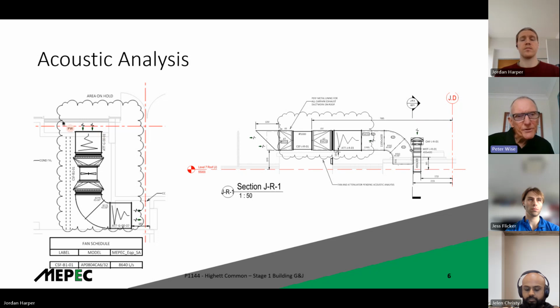Firstly, is this a louver along here? Yeah. So the distance between the louver and the intake to the attenuator should be, let's say, 1 metre - I don't know how much that is here. Then there's the orientation of the splitters in the attenuator, because this is a rectangular attenuator, they can be either horizontal or vertical. In this case they should be vertical because the air's coming through at different levels. If it's horizontal, some air wants to go through certain splitters and you might starve other splitters, giving a very high pressure drop and poor attenuation. So that's one thing.